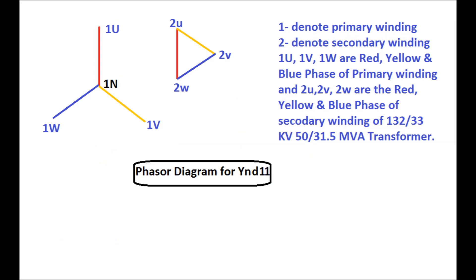Now for the vector group test of YND11 — the phasor diagram for YND11 is shown in this figure. Here, 1U, 1V, and 1W are the red, yellow, and blue phases of the primary or HV winding, and 2U, 2V, and 2W are the red, yellow, and blue phases of the secondary or LV winding of the power transformer.